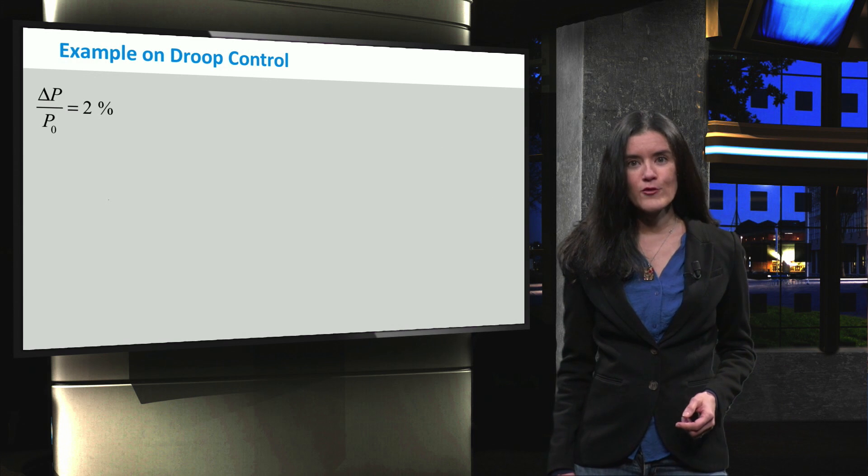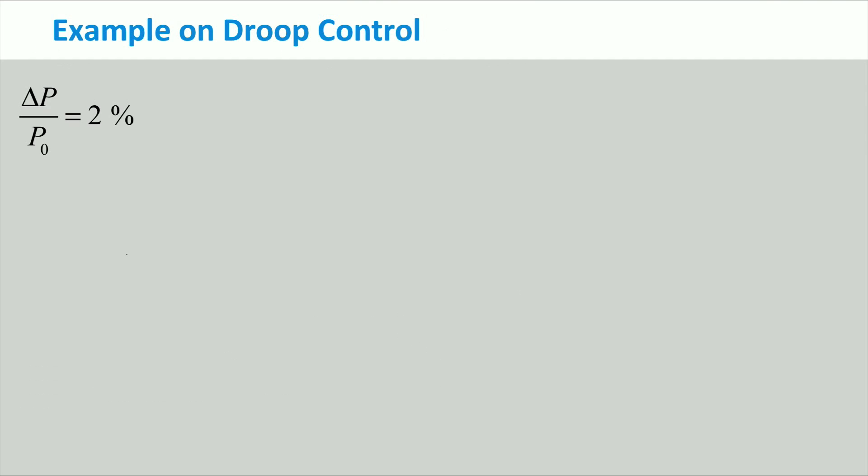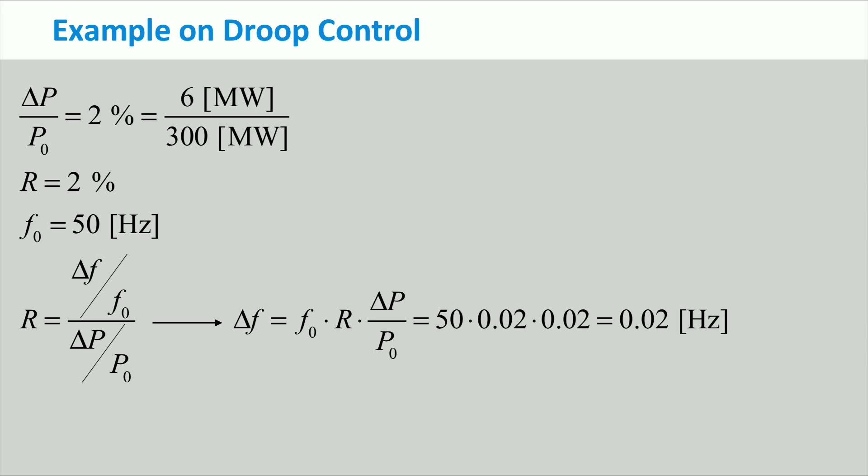Let's have a look at a numerical example. Consider that due to a change in the load, a system suddenly needs to supply an additional 2% from its rated load of 300 MW, meaning 6 MW. The droop coefficient is 2%. If the frequency was at a rated 50 Hz, what would be the new system frequency? Rearranging the droop equation and substituting with the values, we can see that the new system frequency is 49.98 Hz.